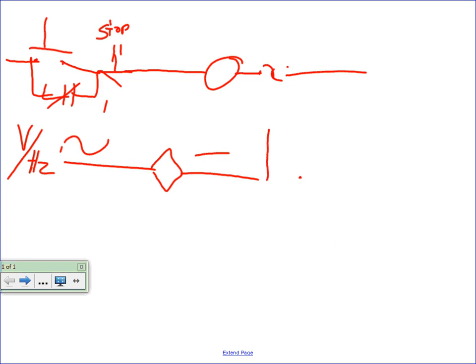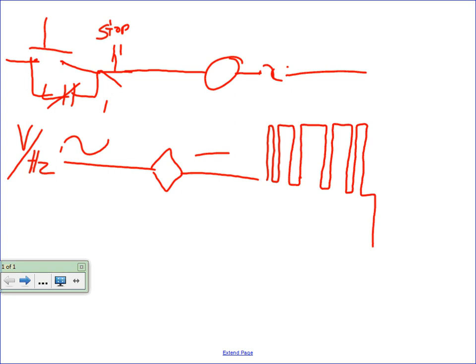So we may, and this is going to be really rough, I apologize, this happens many more times than this, but this will give you the gist of it. Then we do the same thing in the opposite direction. As you look at the different widths of these pulses, the RMS value, when you calculate it out, all of a sudden starts to look like an AC waveform. So the motor doesn't know any difference. It thinks it's seeing an AC waveform when we're actually pulsing DC to it.